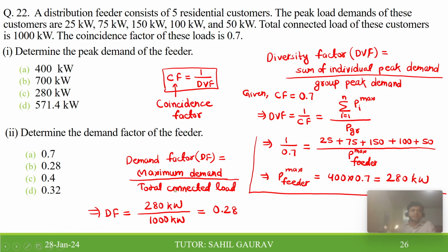So how are we going to find the peak demand of the feeder? That is the group peak demand, because it has five residential customers. Here the coincidence factor is given, so from the coincidence factor we can find the diversity factor. Coincidence factor is just the reciprocal of diversity factor, and we know that diversity factor is the sum of individual peak demands divided by the group peak demand. Here the coincidence factor is given as 0.7, that means the coincidence factor of the feeder is 0.7.